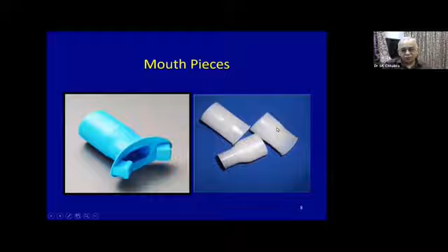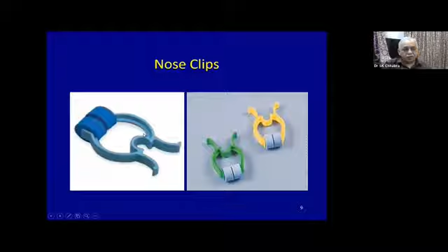But it is very important that when the person is breathing, there is no leak around the mouth. So tight fitting mouthpieces are highly desirable. Now these ones are plastic, or even cardboard mouthpieces are available. There may be a problem of tight fitting, but these are disposable, and that is the advantage of these mouthpieces. Then nose clips. The maneuver is done by mouth breathing. So the nose has to be blocked by these sponged nose clips, which gently press the nostrils so that the person's nose is blocked.